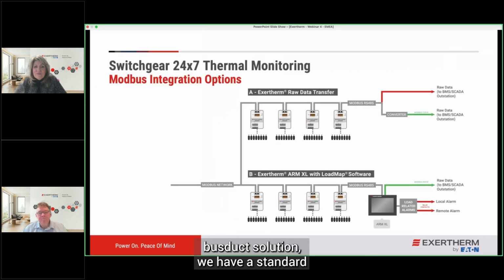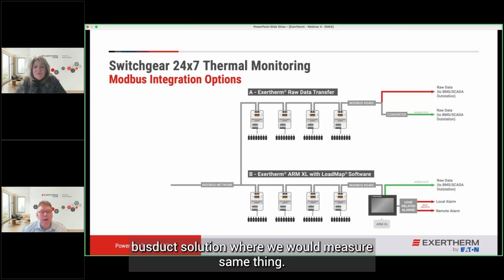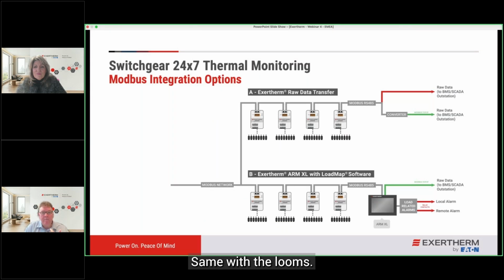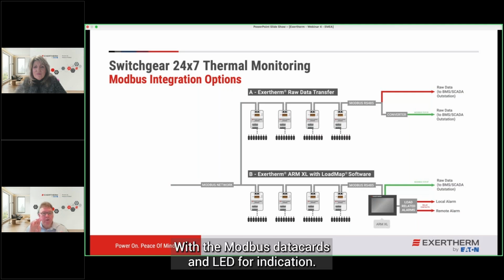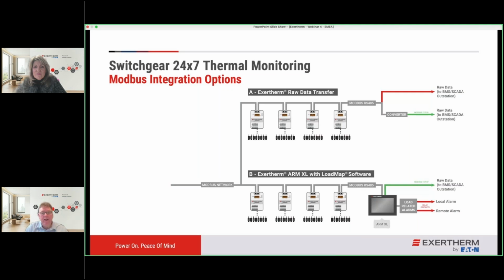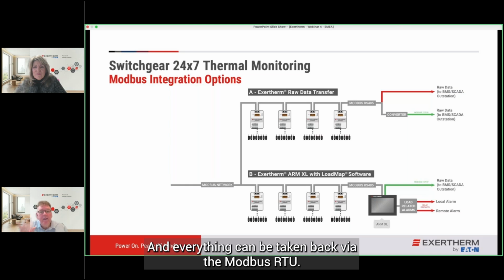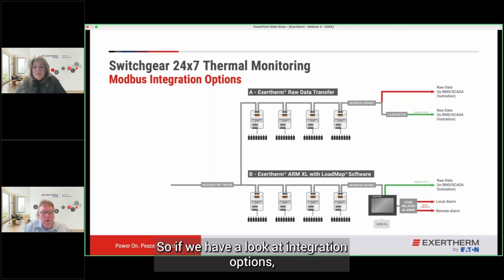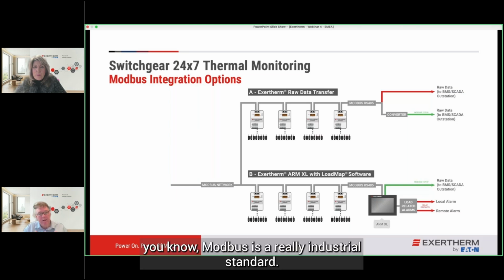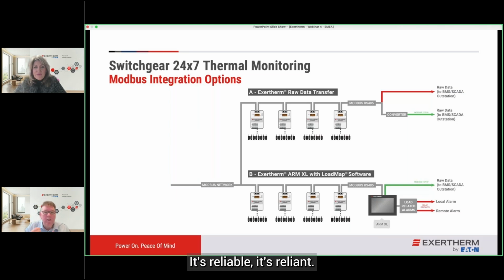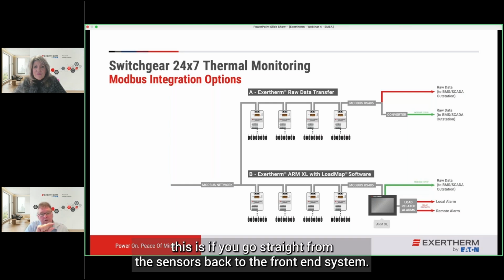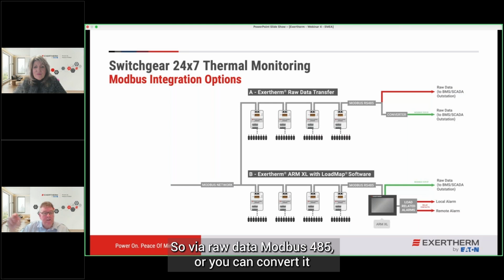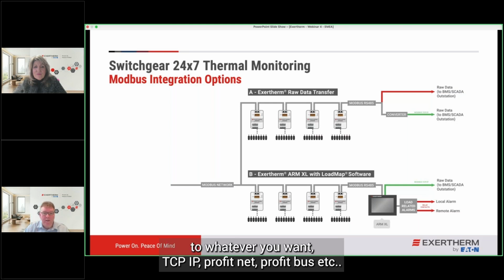On the bus duct solution, we have a standard bus duct solution where we would measure the same with the looms, with Modbus data cards, an LED for indication, and everything can be taken back via the Modbus RTU. If we have a look at our integration options, Modbus is a really industrial standard. It's reliable, and of course, if you look at the top drawing, this is if you go straight from the sensors back to the front end system, via raw data, Modbus 485, or you can convert it to whatever you want: TCP/IP, Profinet, Profibus, etc.